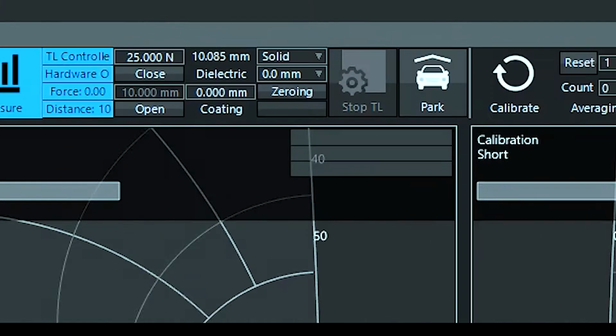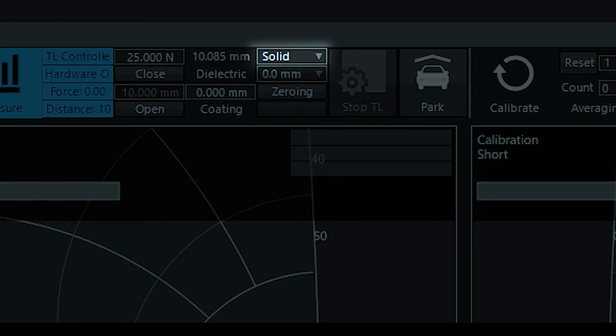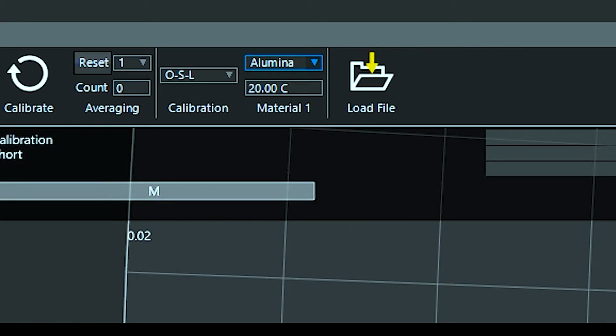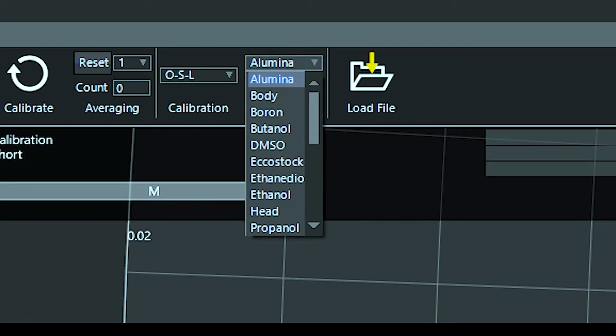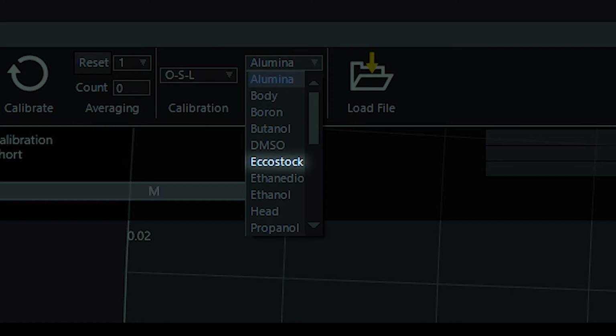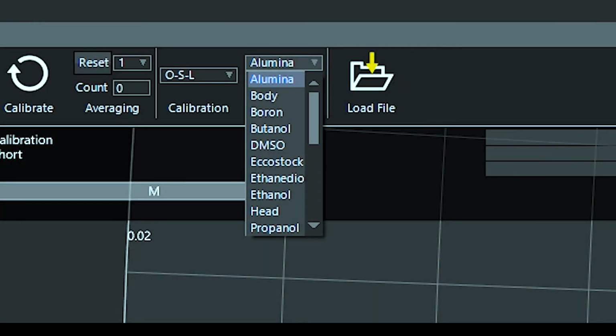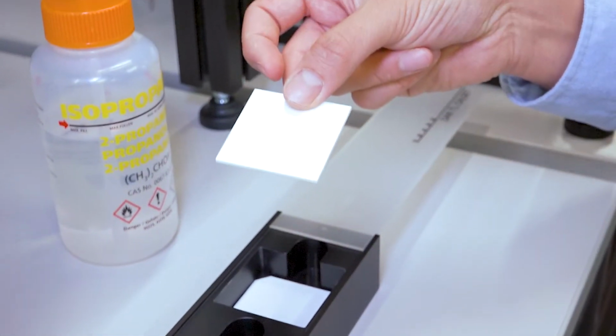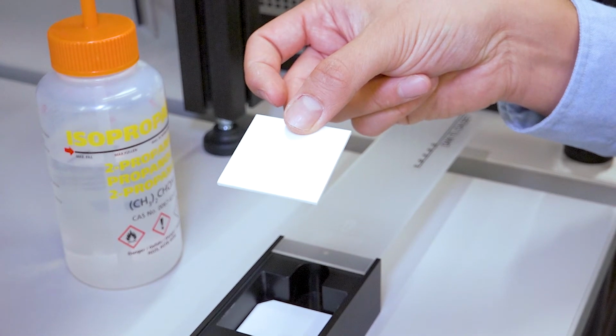Step 1. Measurement mode is set to solid. Step 2. The suitable load material is selected from the drop-down list. We use Eccostock for low permittivity and Alumina disc for high permittivity samples, for permittivity bigger than 10. These materials have well-defined dielectric parameters that are frequency independent over DAK-TL2's entire frequency range. In addition, the discs have polished surfaces that make good contact with the probe flange.